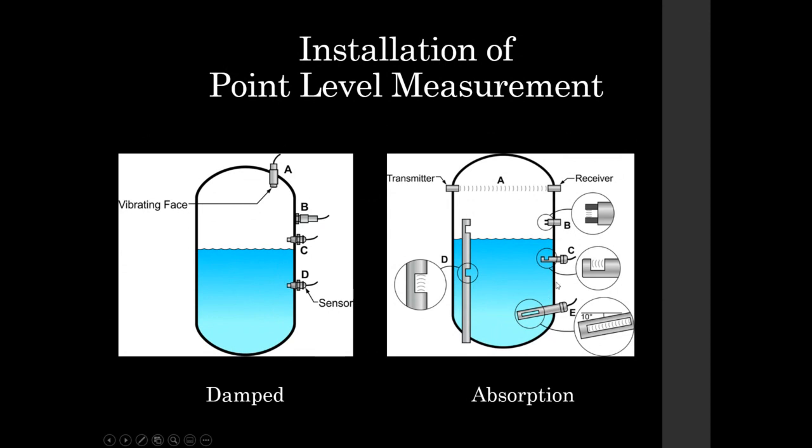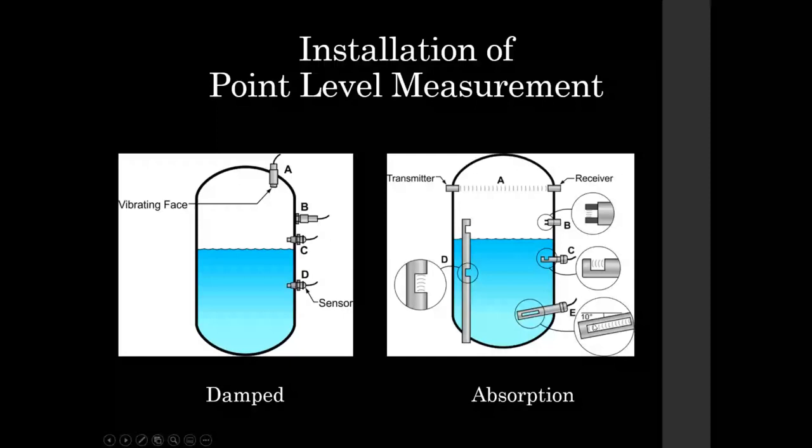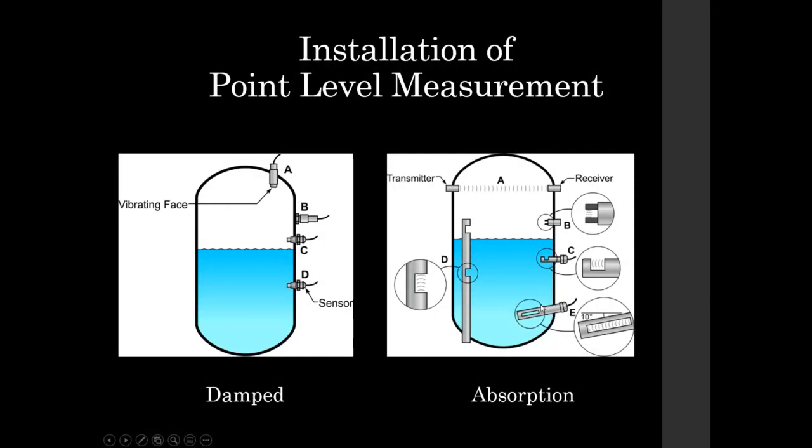Absorption style, the only difference between the absorption style really and the damped style here is that this particular application down here, E, by tilting it at a little bit of an angle, does give you a little bit more of a dead band in that switching situation, but for the most part, the installation characteristics are the same here. They don't activate until they become submerged entirely, and the difference in frequency is sensed by the electronics. So that was a pretty quick little thing of ultrasonic, and that's good.